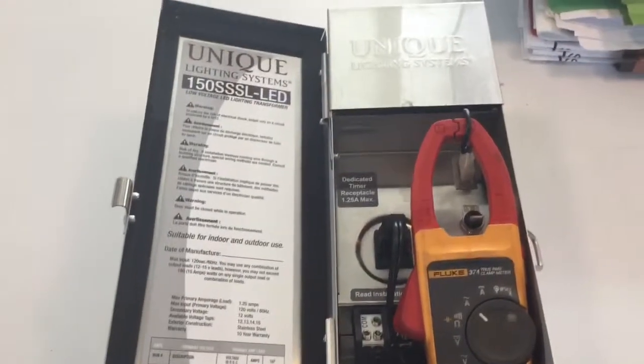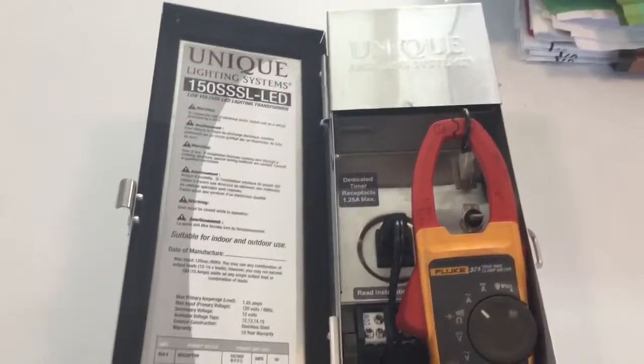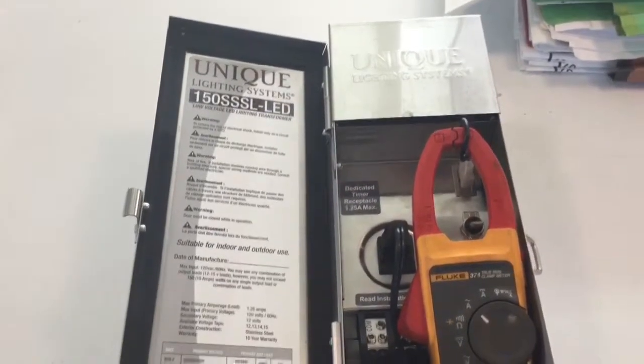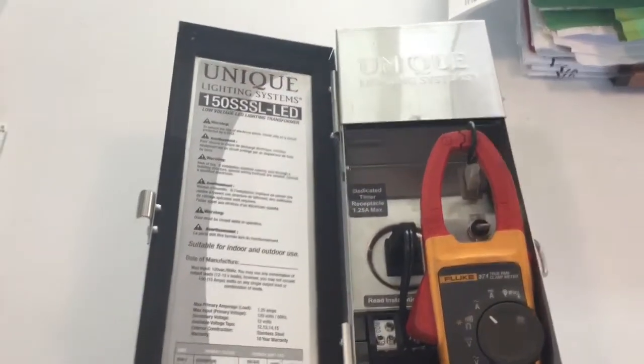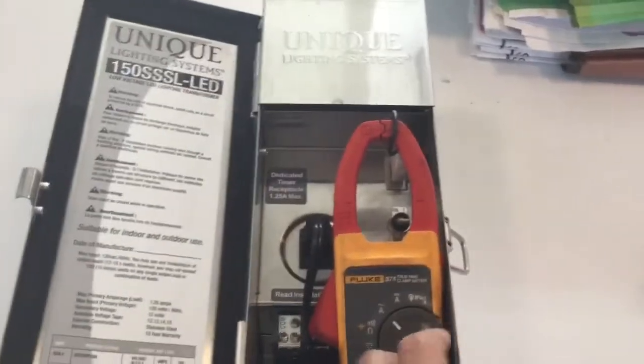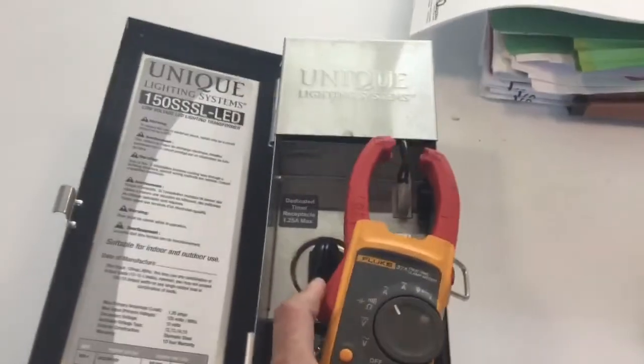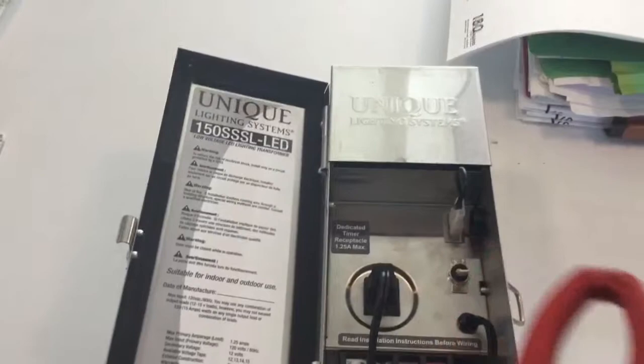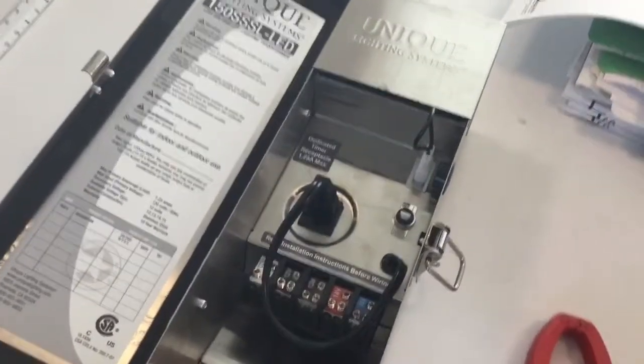If you're at 1.2 or 1.25, this transformer is fully loaded, and you may start experiencing some shutdowns or overheated transformers that are going to shorten their lifespan because they're just working too hard. So at that point, you've got to think about a bigger transformer.